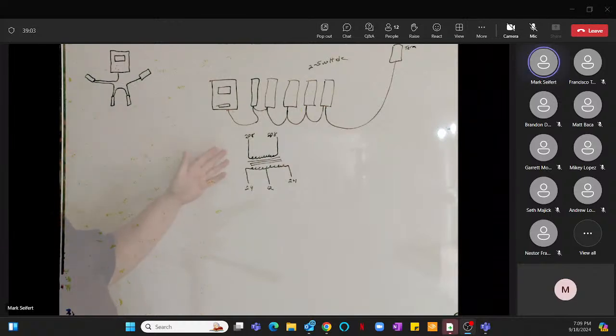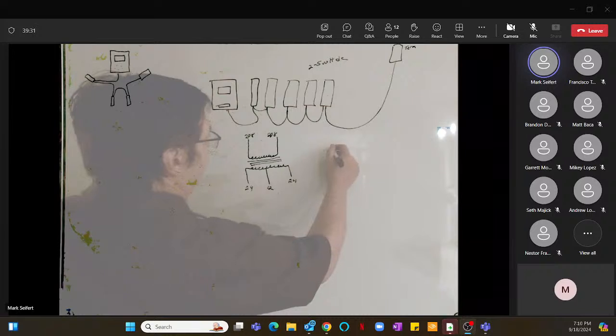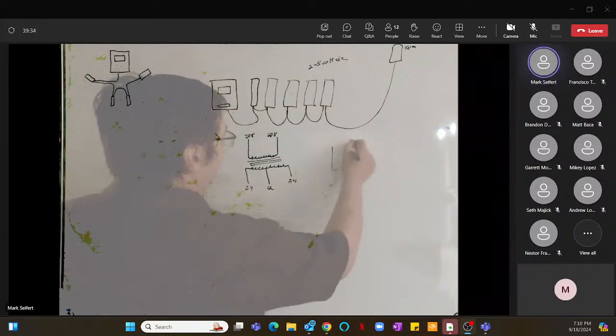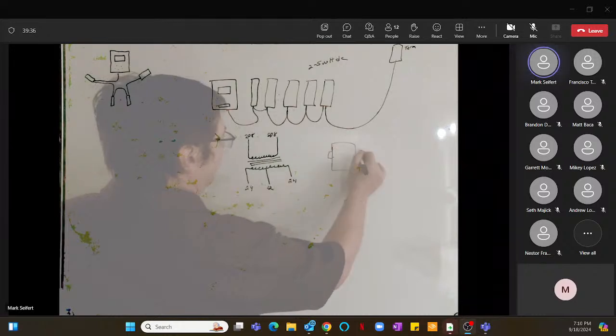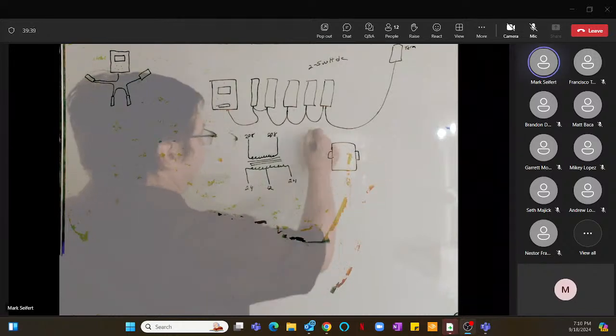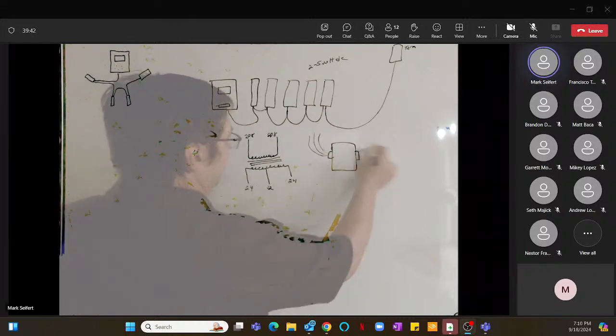Now, when we have a bad transformer, we don't have to use the exact same one. As long as the VA is correct, any multi-branch transformer will work. And that's what I've been buying because you're never going to find a control transformer unless they're old ones that we have. So I have bought the regular transformers that just have the bunches of wires coming in and bunches of wires coming out.